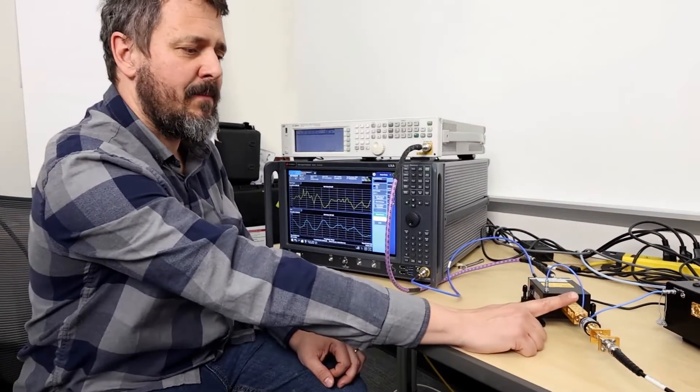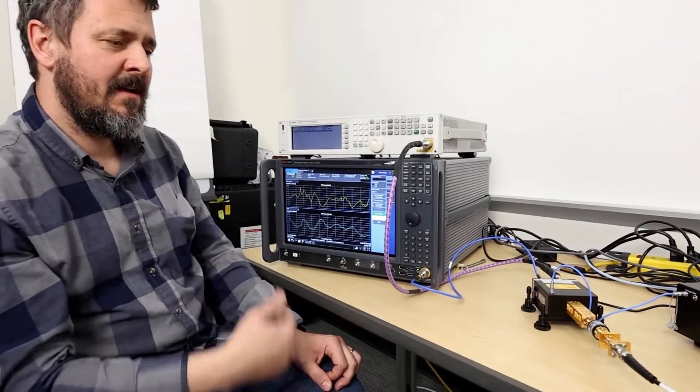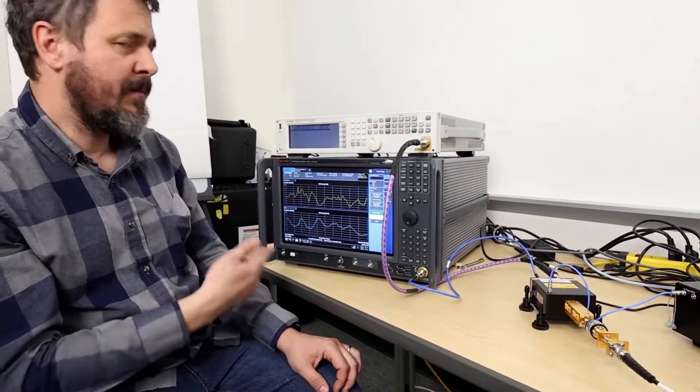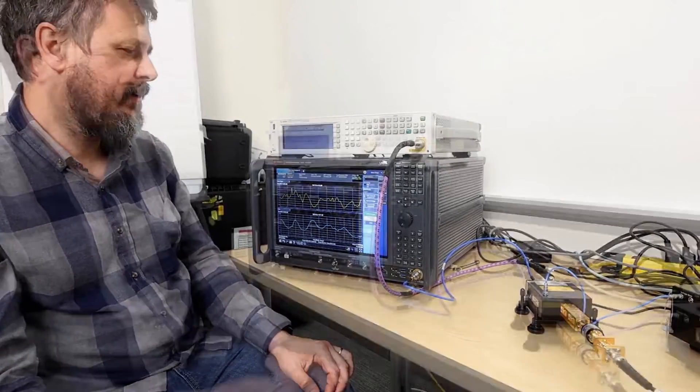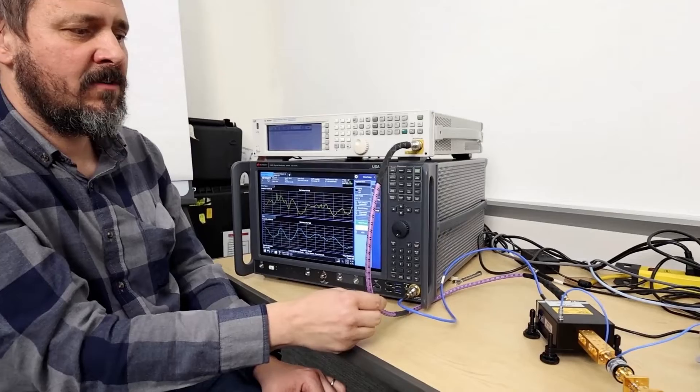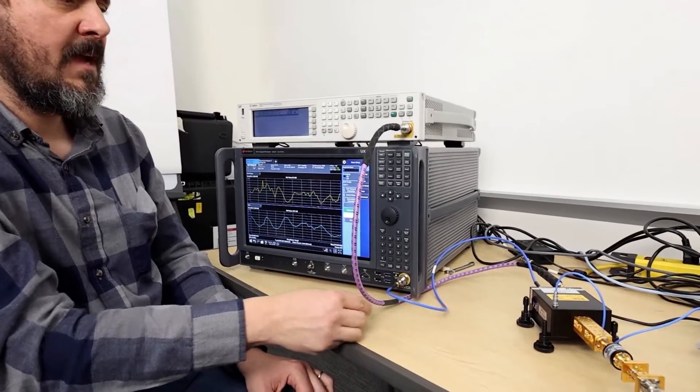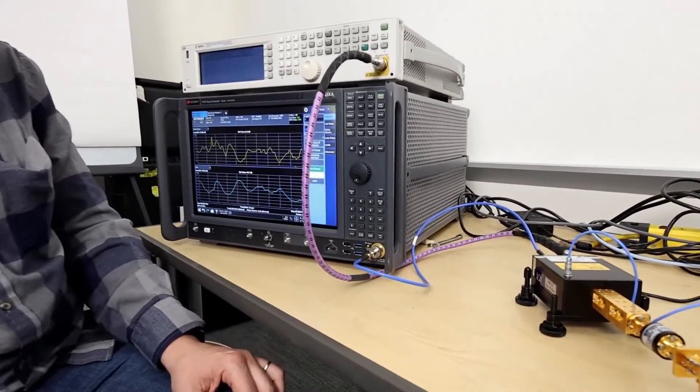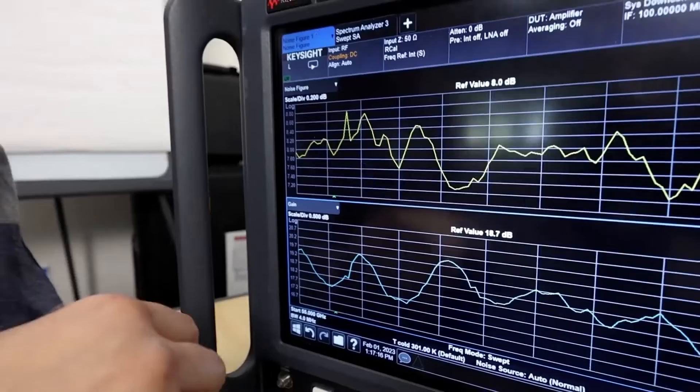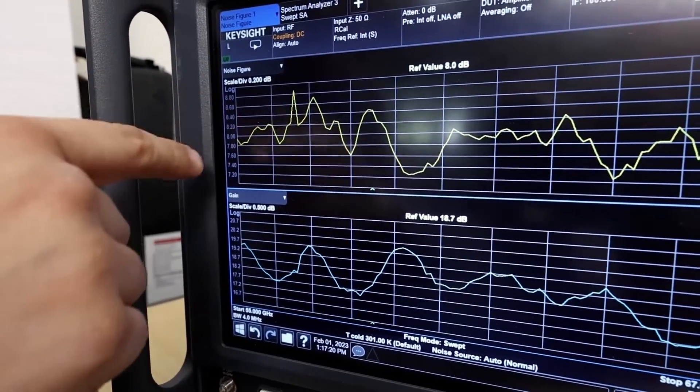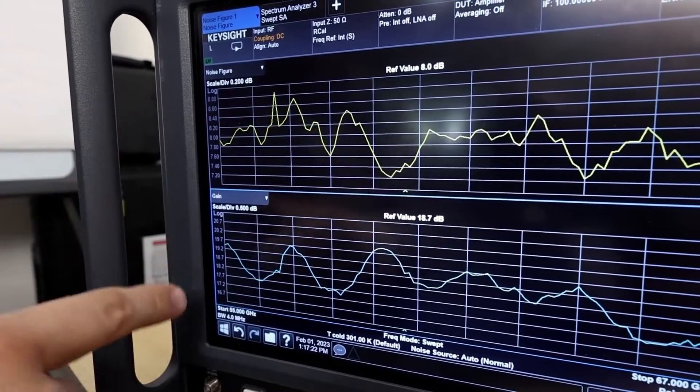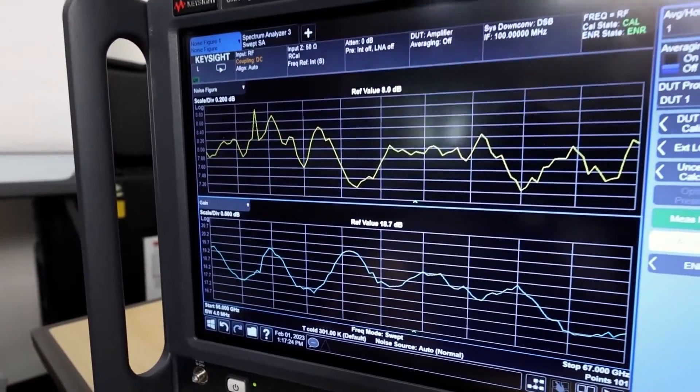I've connected up our amplifier and now I'm making our noise figure measurement. And I'm getting similar results to what I got using the frequency range extender. I'm using an MXG as our LO source. And so the LO is being doubled inside the VDI downconverter. Now I've put in our DUT and we're getting similar results to what we got with the frequency range extender, which is about 8 dB of noise figure and about 19 dB of gain.